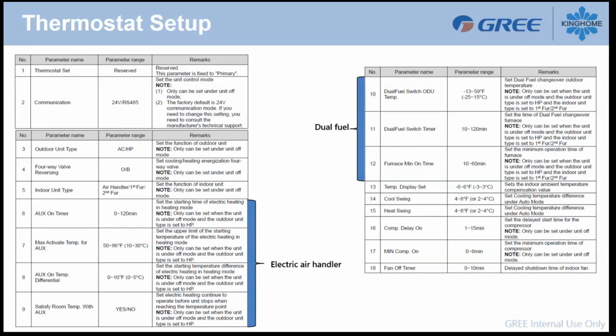Number 7 is maximum activate temperature for aux. This is regarding the outdoor temperature. If you have the Wi-Fi connected or an optional outdoor sensor connected to the system, we will take a reading of this outdoor temperature, and between 10 and 30 degrees Celsius, you can apply a limit to start the duct heater. So for example, if I set it to 10 degrees Celsius, if it's more than 10 degrees Celsius, my duct heater doesn't have the right to run.